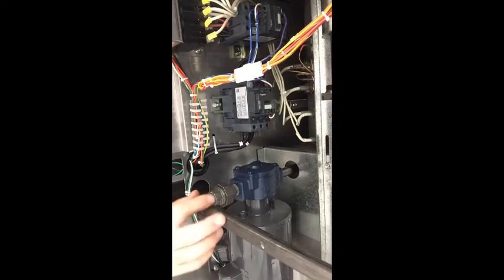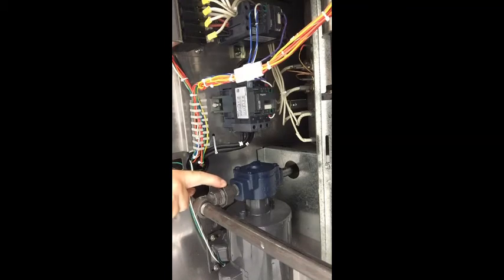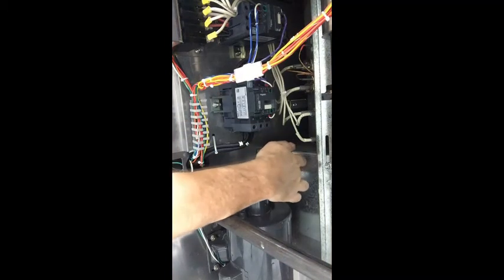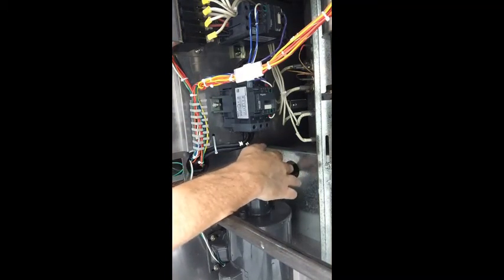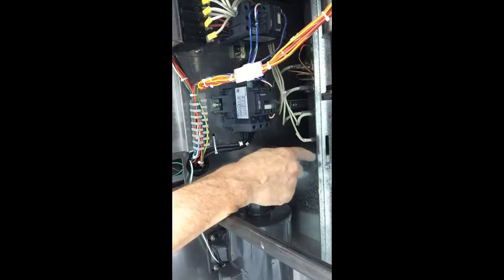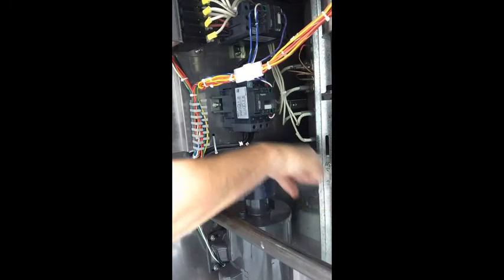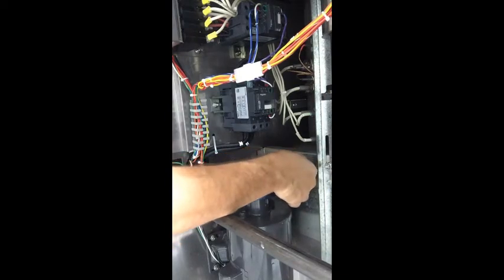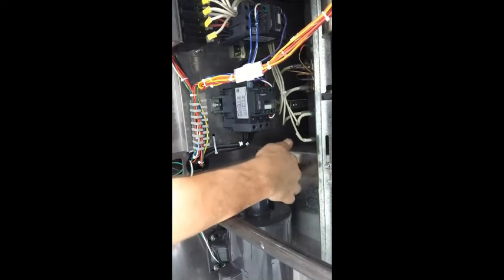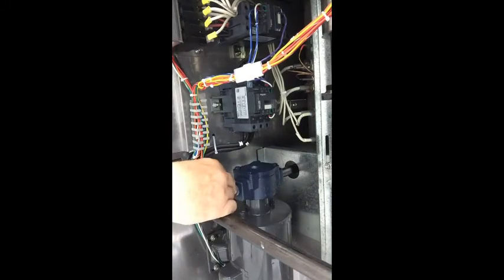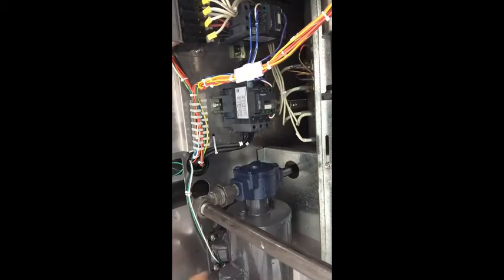Now, if we were going to remove this filter pump, all you'd have to do is break this union here. This pipe right here goes out to that quick connect for the filter pan. Take the quick connect off the other end of it, or you can just unscrew it from here. Take your pipe wrench, unscrew it from here, and slide it forward. But that'll allow this to come out then. And that's it. You've got two fittings right there.